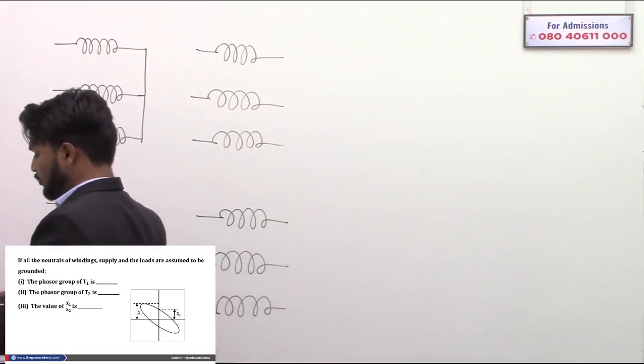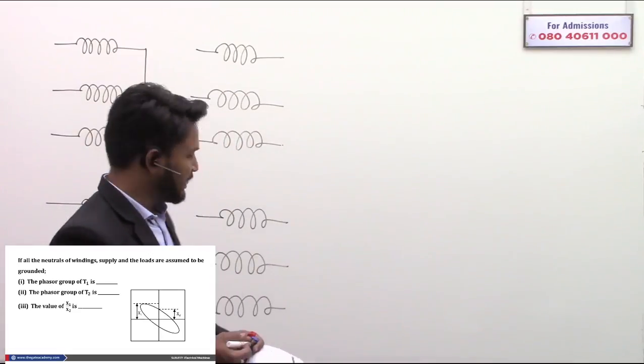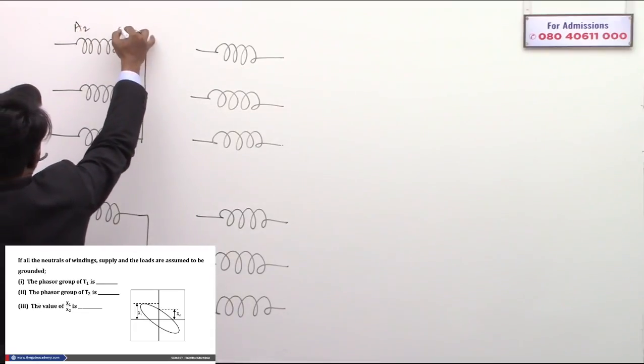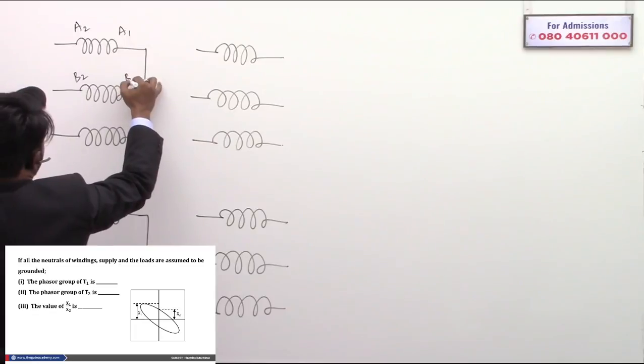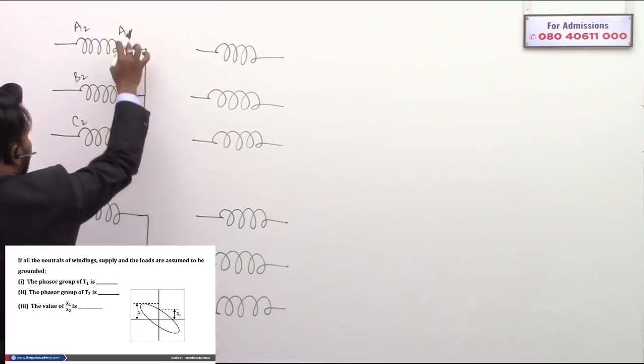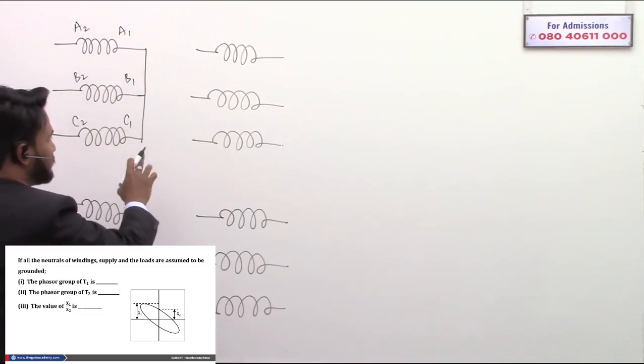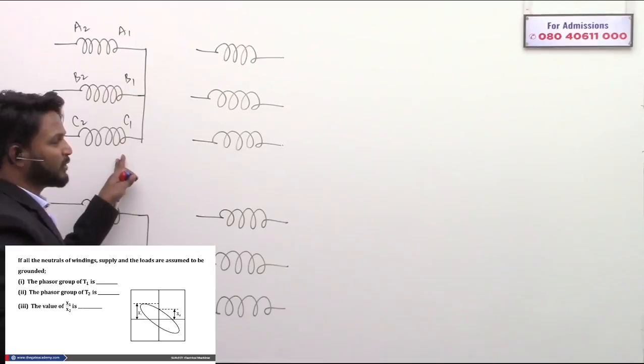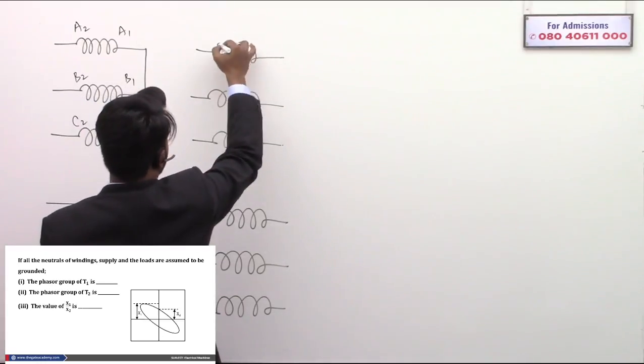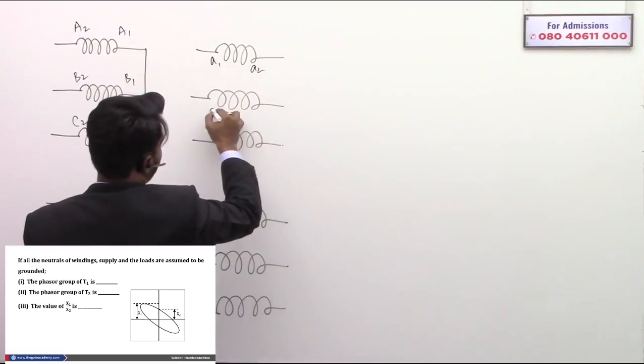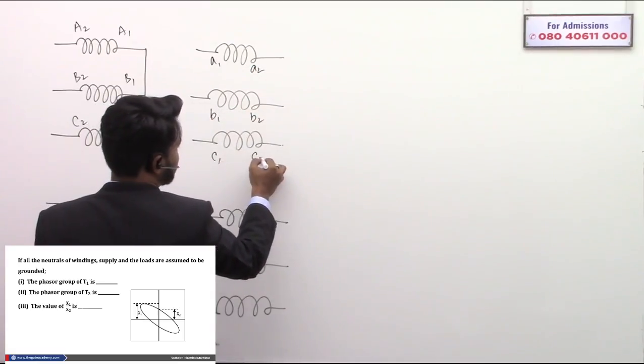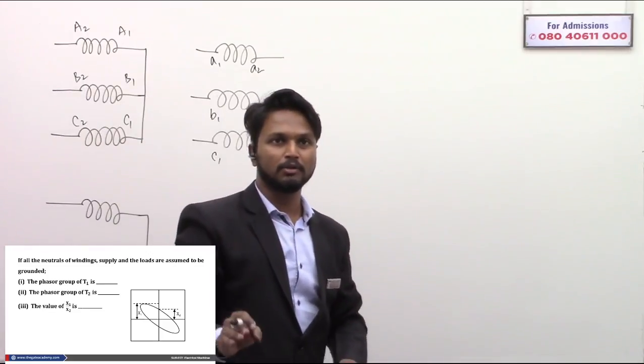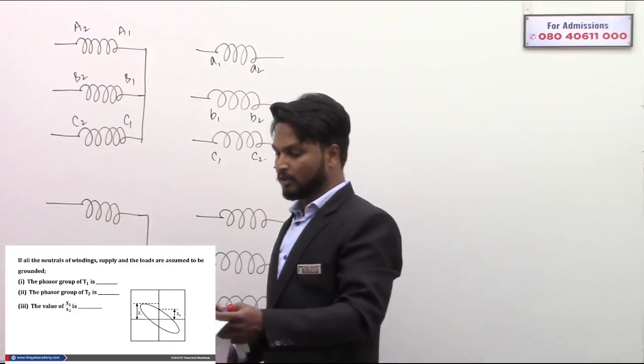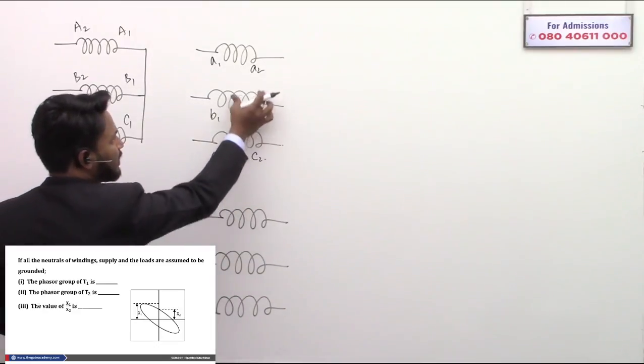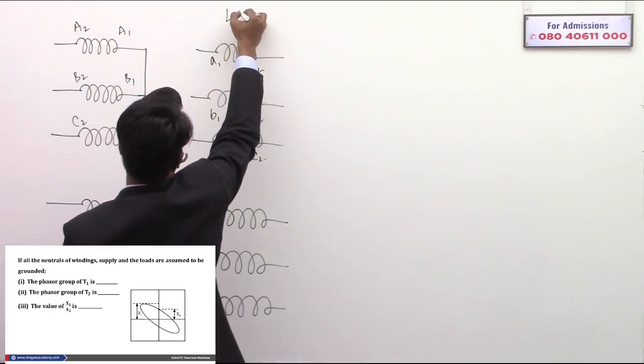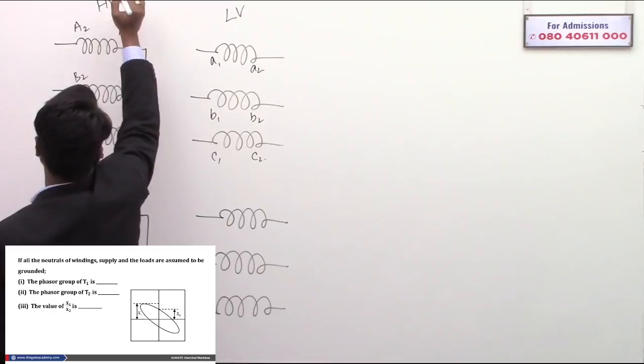If you look at the terminals: A1, A2, B2, B1, C2, C1 — A phase winding, B phase winding, C phase winding. If indicated in capital letters, they belong to the HV side. If indicated in small letters (a1, a2, b1, b2, c1, c2), you should be well versed with this nomenclature, otherwise you cannot answer the question. Small letters mean they belong to the LV side — this is the low voltage side, and this is the high voltage side.